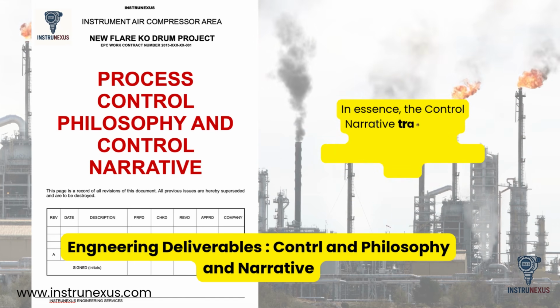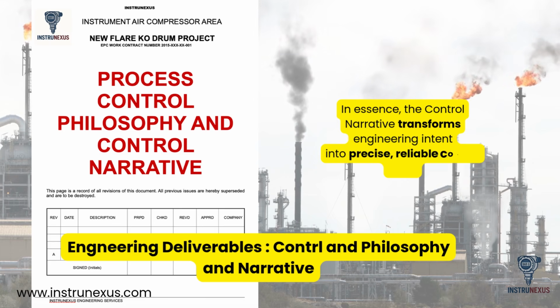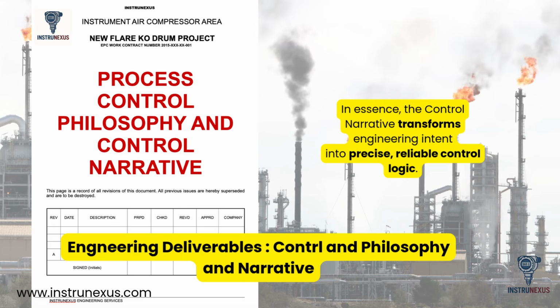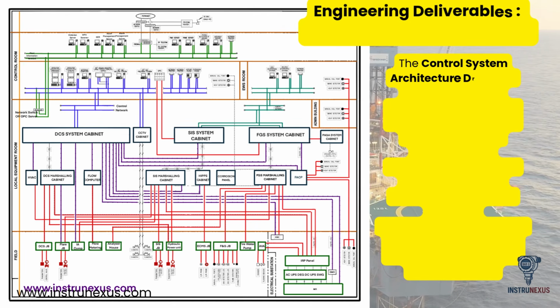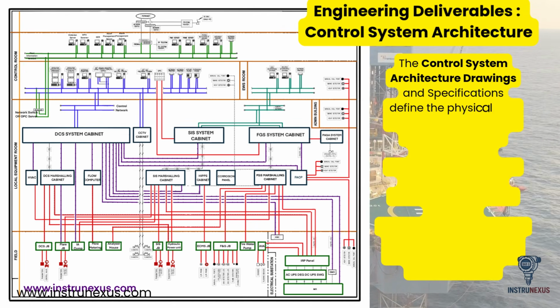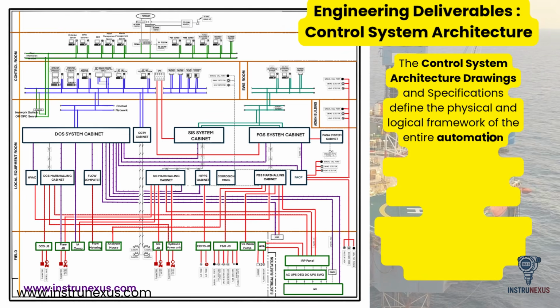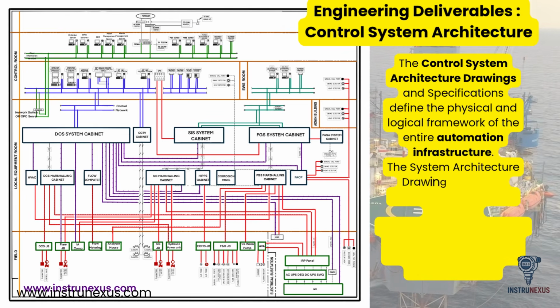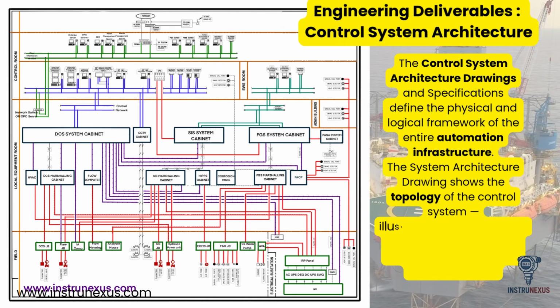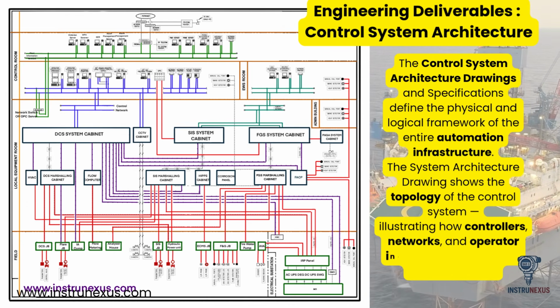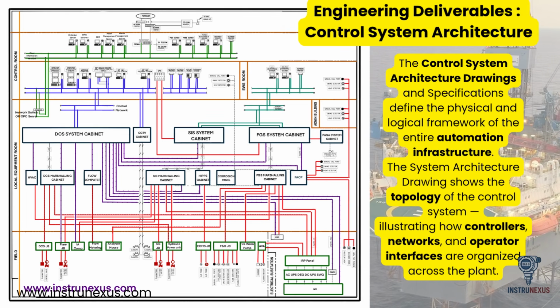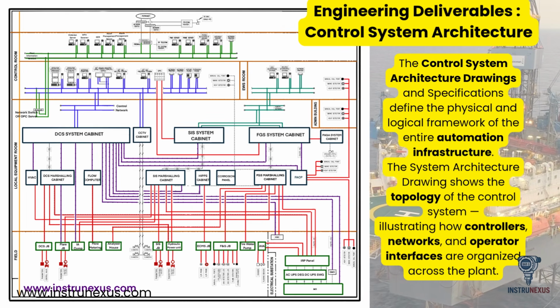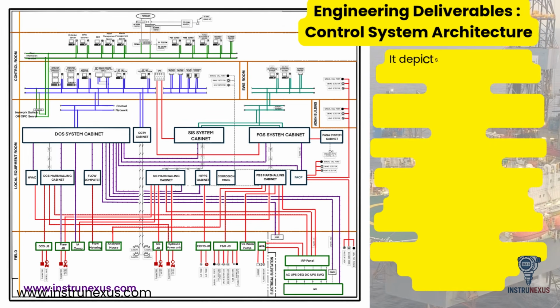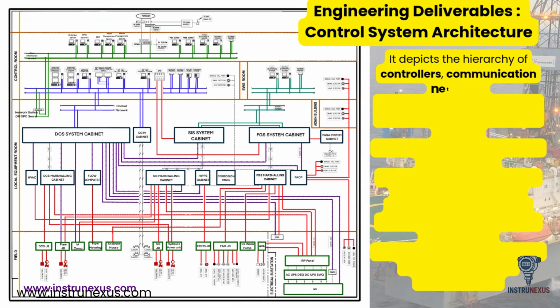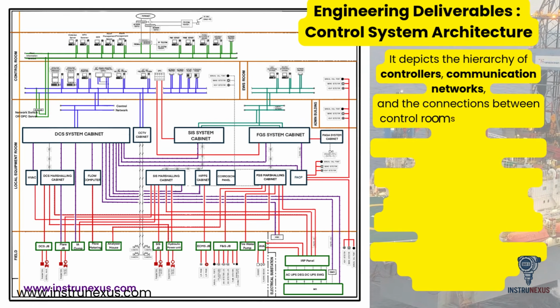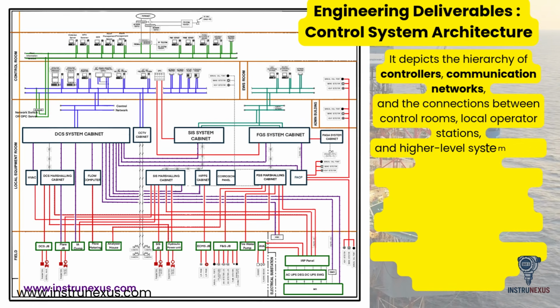In essence, the control narrative transforms engineering intent into precise, reliable control logic. The control system architecture drawings and specifications define the physical and logical framework of the entire automation infrastructure. The system architecture drawing shows the topology of the control system, illustrating how controllers, networks, and operator interfaces are organized across the plant. It depicts the hierarchy of controllers, communication networks, and the connections between control rooms, local operator stations, and higher-level systems such as MES or ERP.